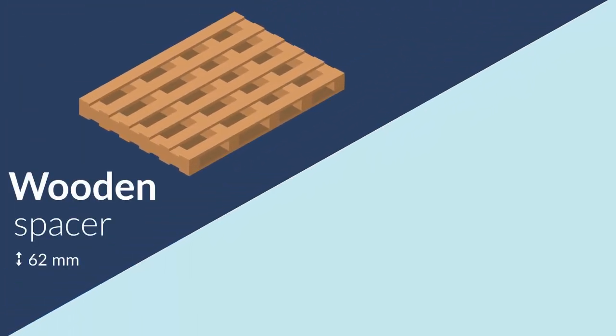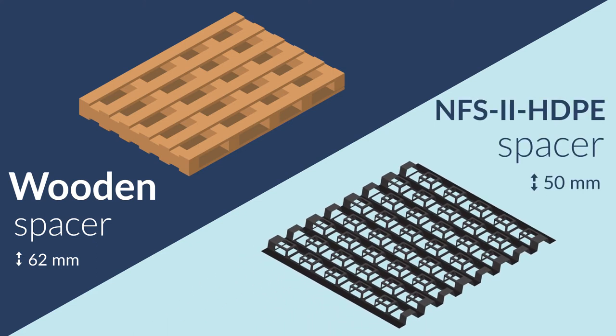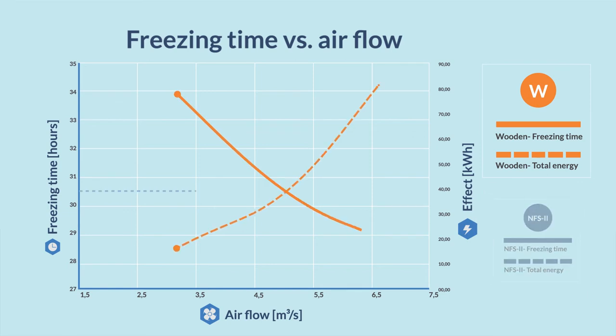We compared 62mm high wooden freezer spacers with Freezetech's own 50mm high NFS2 HDPE spacers. It is remarkable just how much energy is required to shorten freezing time. Based on a freezing time of 30.5 hours, the wooden spacer required an airflow of 4.75 m³ per second and 39 kWh of energy. The airflow with Freezetech's NFS2 spacer could be reduced to 2.9 m³ per second, which reduced the energy consumption to 19 kWh — a 50% saving under identical conditions.